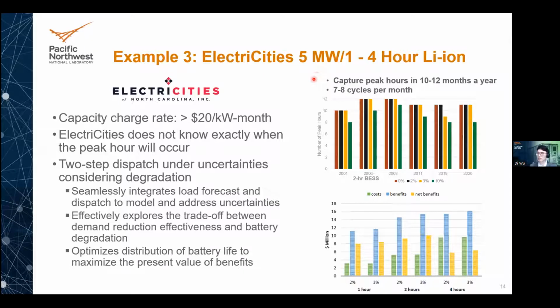Here is the cost versus benefits and also the net benefits. As can be seen, the 2-hour battery energy storage results in the maximum net benefits. On the other hand, 4-hour battery energy storage can help mitigate the risk of missing the system peak load, and the increased duration also helps mitigate battery degradation by reducing the depth of discharge.